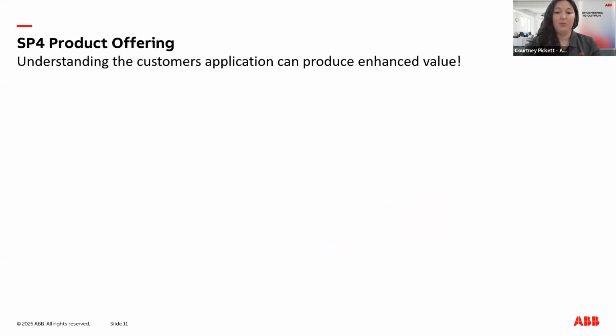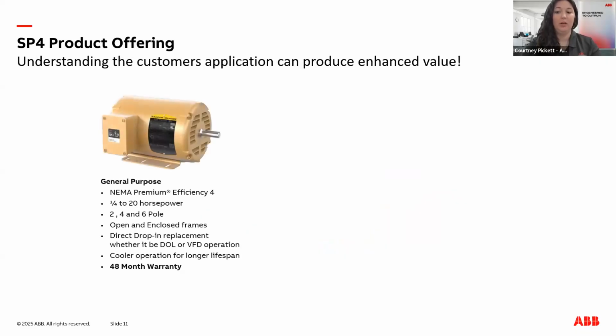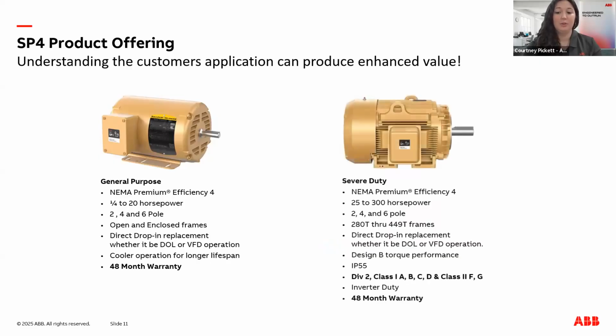Now, the SP4 platform is designed to meet you where you are, whatever your application looks like. We offer our general purpose motors in rolled steel with the standard and our C-face options. And for those tougher environments, our severe duty line spans up to 300 horsepower and includes hazardous location ratings. Both of these lines are drop-in ready for your direct online or VFD operations. And no matter the configuration, every SP4 motor comes with our 4-year warranty, because performance should come with peace of mind.